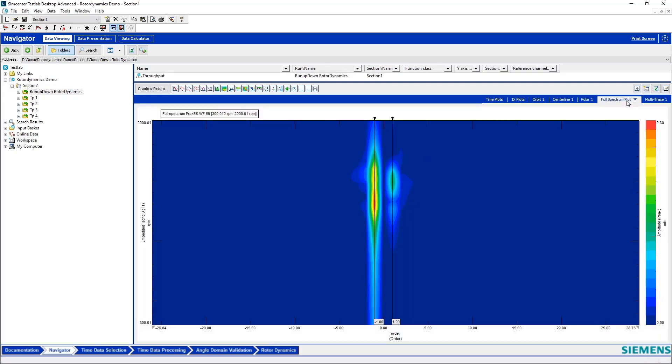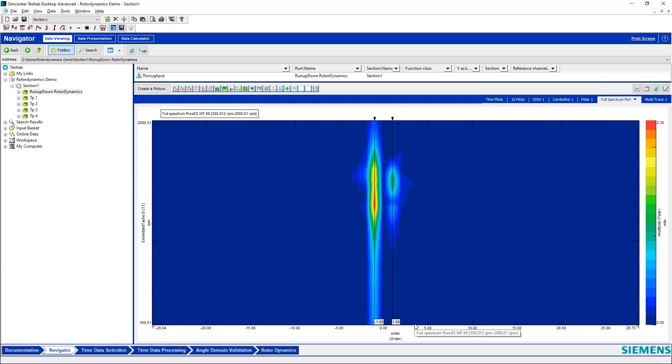Finally, I've got a full spectrum plot plotted from that RPM range from 300 to 2000 RPM. And here you can see that I start on this particular machine with very little forward first order vibration and a small amount of negative first order vibration. And then finally when I get into that rotational speed about where my resonance is located, I can see that I have a strong negative first order component and a weaker first order component.